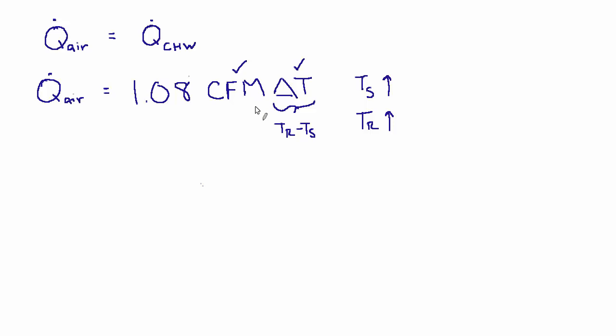But the hope is that we're able to offset that slight increase in fan energy by getting more energy savings back at the chiller. And I wouldn't assume that that's true. I would always want to trend this and test and measure and confirm that it's true in your particular building. But in general, because it's a central system, we're only talking about a slight increase of fan energy in certain zones. Other zones might not be affected. But the chilled water supply temperature that we increased is now increased for the entire system. So that's a big win. It's a centralized global win for the whole building.